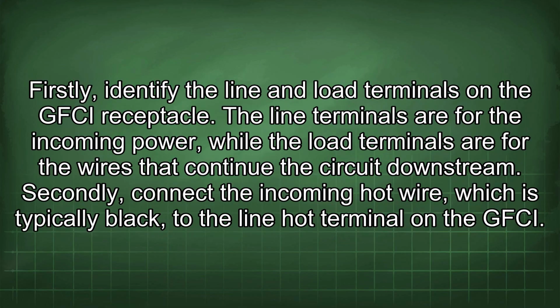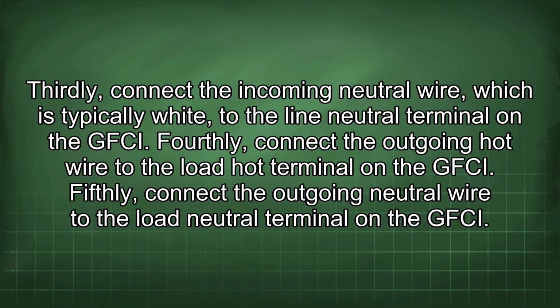Firstly, identify the line and load terminals on the GFCI receptacle. The line terminals are for the incoming power, while the load terminals are for the wires that continue the circuit downstream. Secondly, connect the incoming hot wire, which is typically black, to the line hot terminal on the GFCI. Thirdly, connect the incoming neutral wire, which is typically white, to the line neutral terminal on the GFCI.